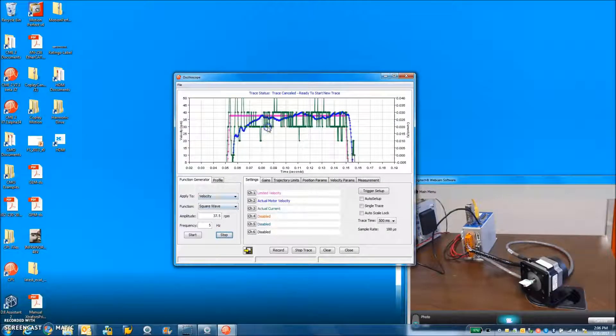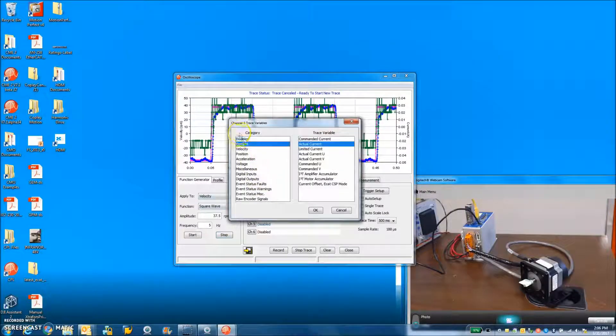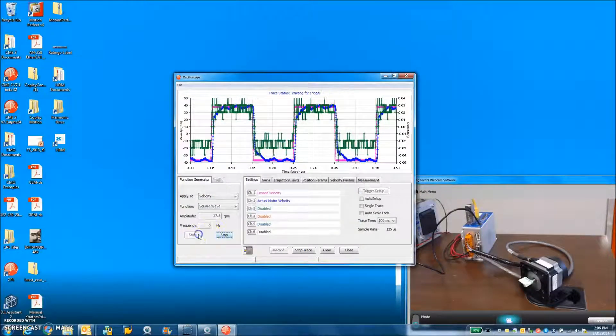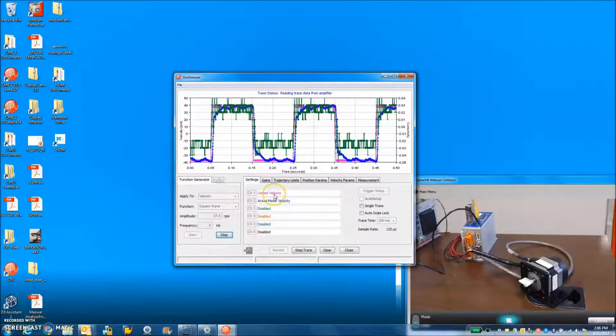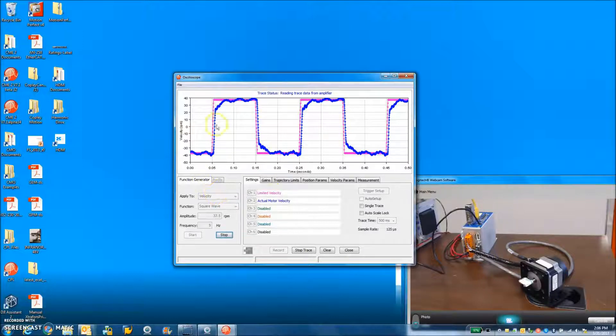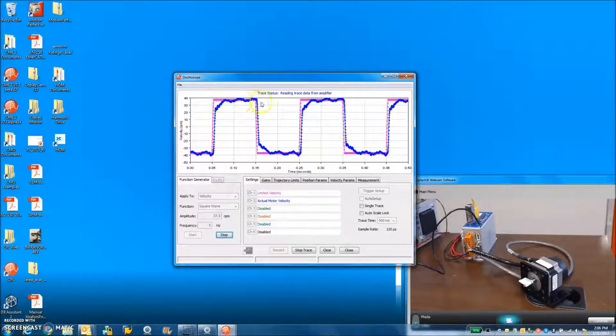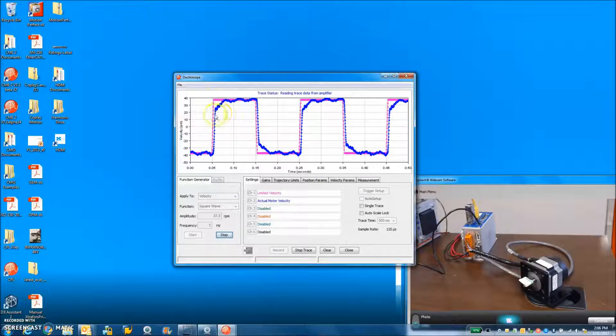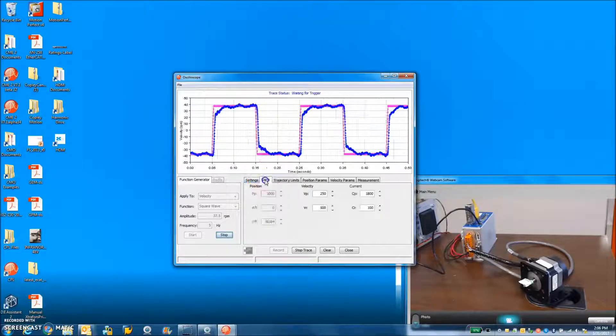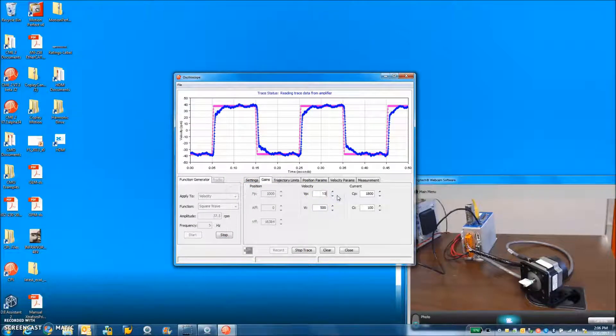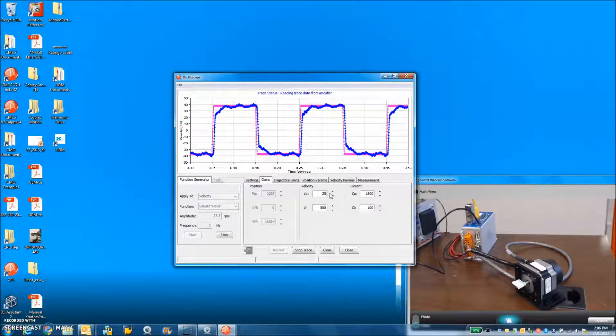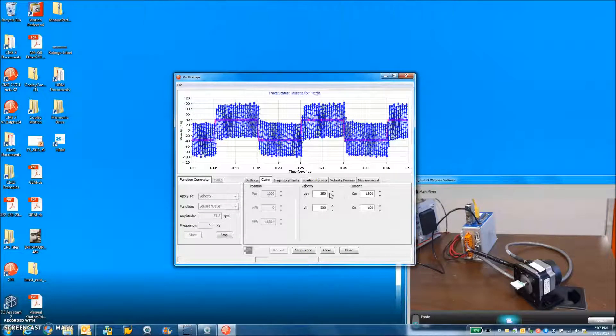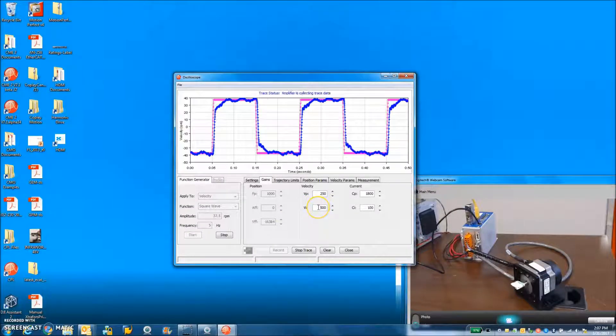So it's just a little wiggle in the motor as I'm testing out the velocity mode. I can see, yeah, the current's nice and small. Let's get that out of there. It's square wave and it goes through an accel/decel limit. And so I have commanded and then actual and it's a little bit bumpy. But if the gains are too high and cut the gains in half if the gains get too high. There you go. Big oscillations. I cranked up the integral term. That seems to be fine.